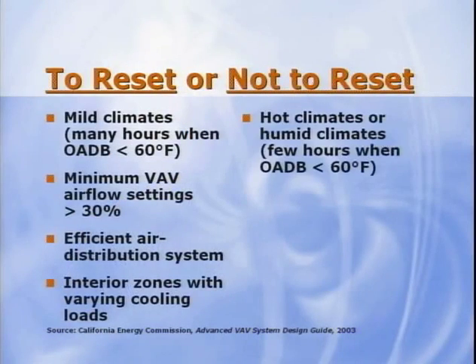On the other hand, conditions that reduce the potential to save energy with supply air reset include hot or humid climates that have relatively few hours when the outdoor dry bulb temperature is below 60 degrees Fahrenheit. Humidity is a condition that adversely affects comfort.